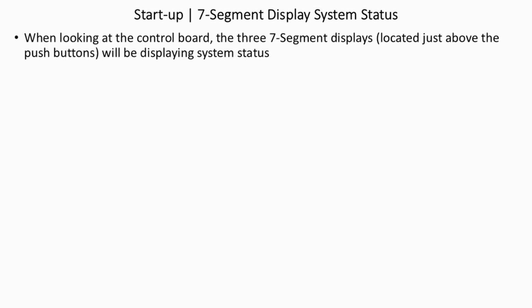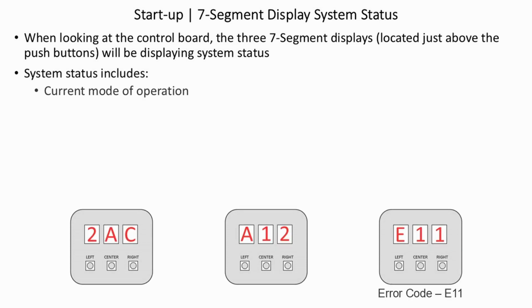Startup 7-segment display system status. When looking at the control board, the 3 7-segment displays, located just above the push buttons, will be displaying the system status. System status includes current mode of operation, as shown in the example below on the left, 2 AC, air conditioner, high stage. Airflow, as shown on the example below in the center, A12, airflow 1200 CFM.